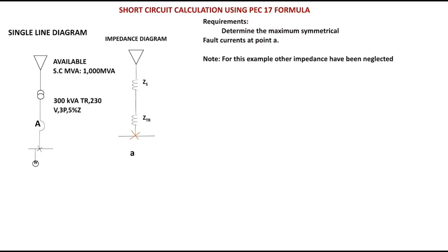And then this is the requirements. Determine the maximum symmetrical fault currents at point a. So we need to determine what is the short circuit current at point a so that we can size the circuit breaker to be installed on this circuit. Note, for this example, other impedance have been neglected. So this is our example, and then we use the formula for the source impedance.